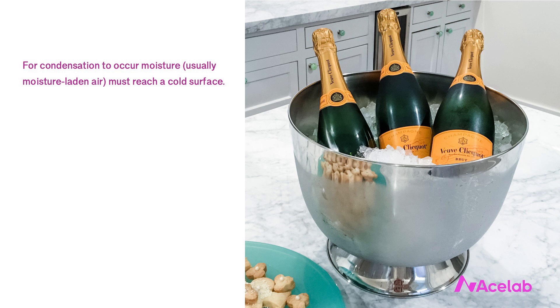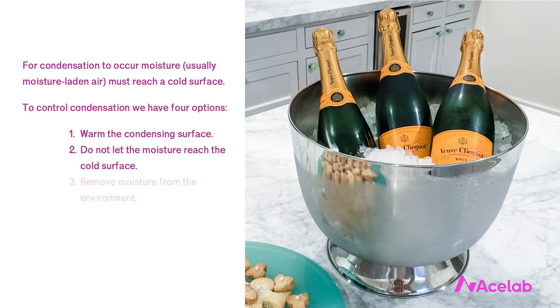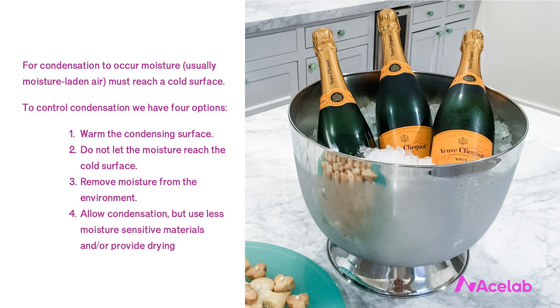For condensation to occur, moisture — usually moisture-laden air — must reach a cold surface. No cold surface, no condensation. To control condensation in buildings, we have four options: one, warm the condensing surface, preventing the problem from occurring by not having anything cold; two, prevent moisture from reaching the cold surface; three, remove moisture from the environment, perhaps by dehumidifying; and four, allow condensation to occur but make it so it doesn't present a problem, either by using materials that aren't moisture-sensitive or by providing drying.